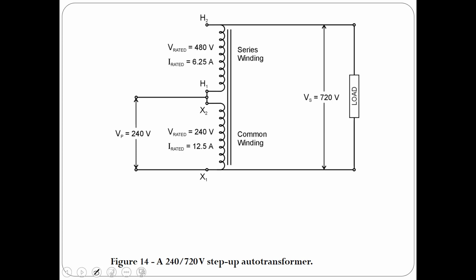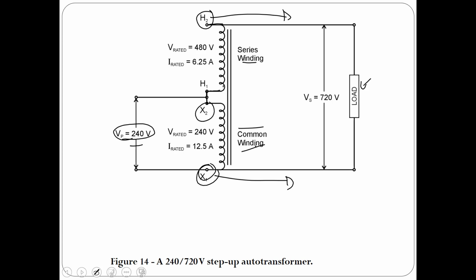Let's have a look before we continue. We're going to put our 240 volts between X1 and X2. In this case, H1 is connected up to X2, so it's in series with the X winding, and we're going to connect our load between H2 and X1. So we've made a step-up autotransformer. Let's look at these rated values. This is step up, so the series winding is in series with the load. The common winding is common with the supply voltage. The rated current of the series winding, the maximum, is 6.25 amps. The rated current of the common winding is 12.5 amps.